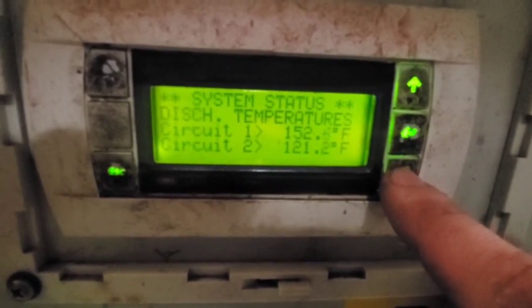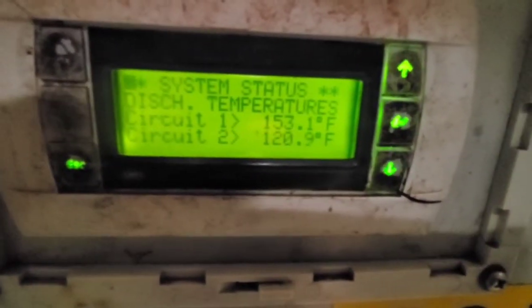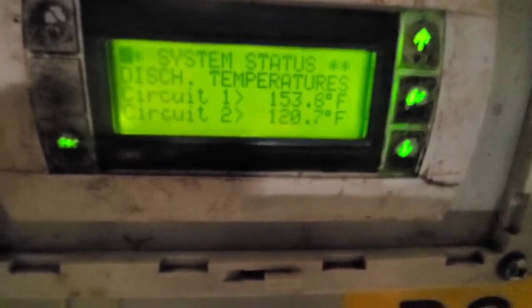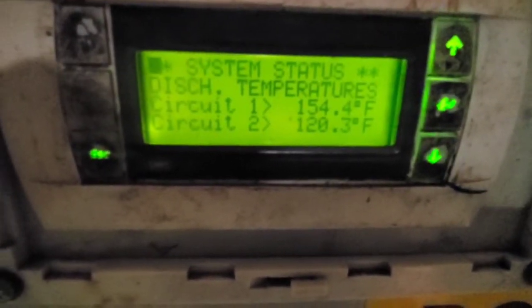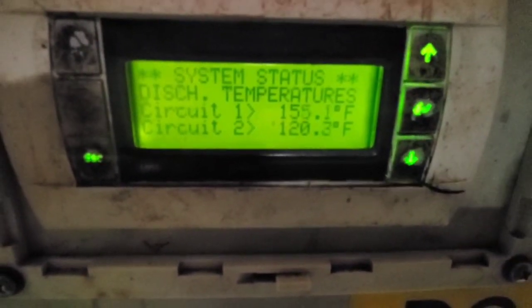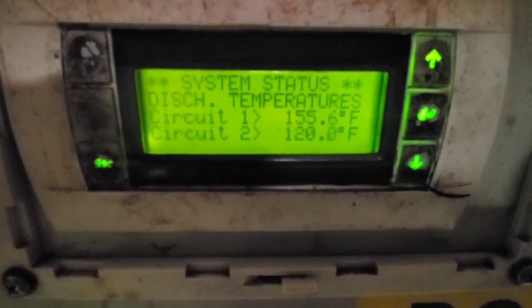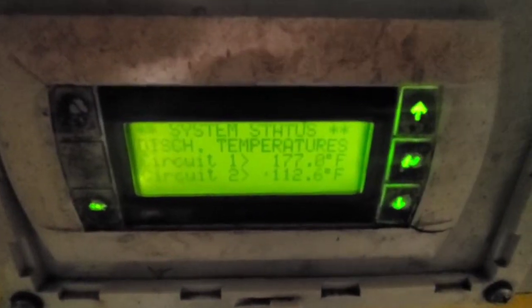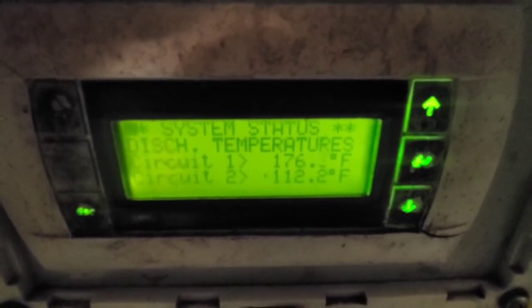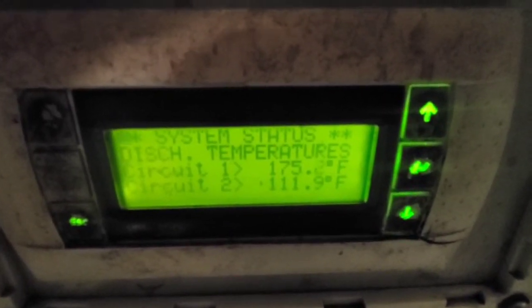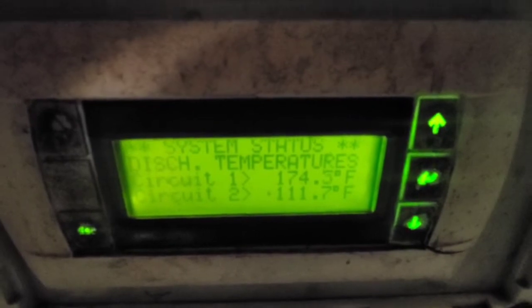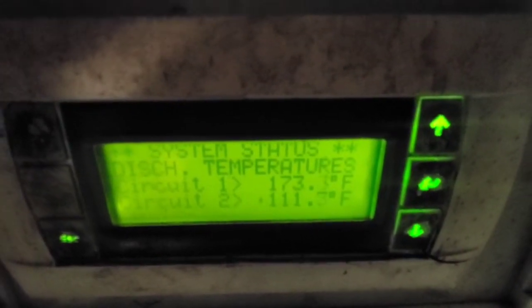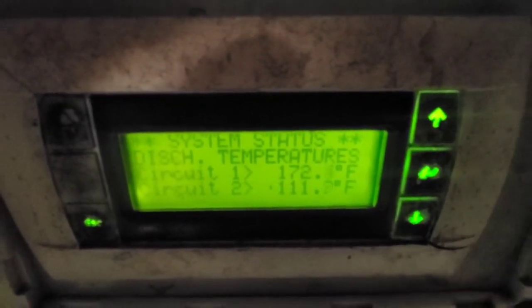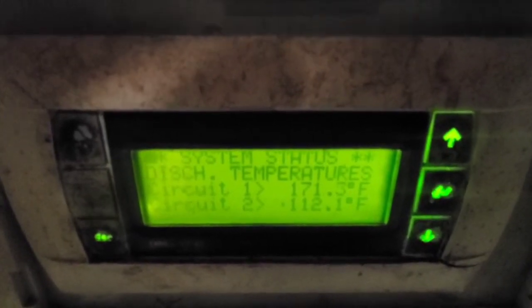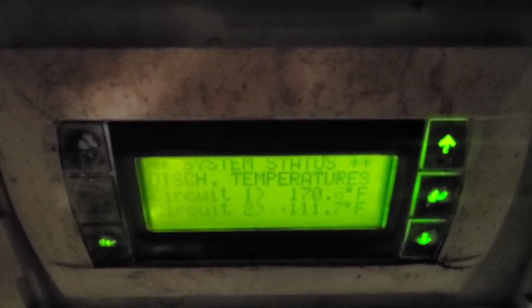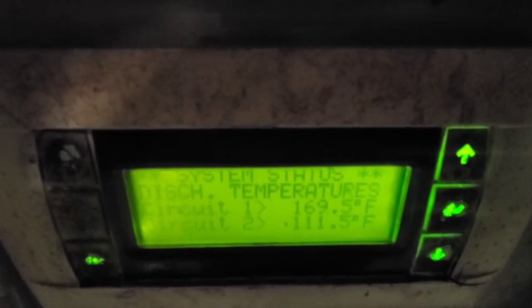The other thing that we look at is circuit 1 discharge temperature. We're going to observe that for a little bit and make sure that the oil is cooling the compressor good enough to keep that oil temperature under 180 degrees. So at 180 degrees, a solenoid energizes that allows our oil cooler circuit to start cooling the oil down. As you can see, it's going to drop the oil temperature down to around 160, and then when it gets back up to 180, it'll cool it back down again.